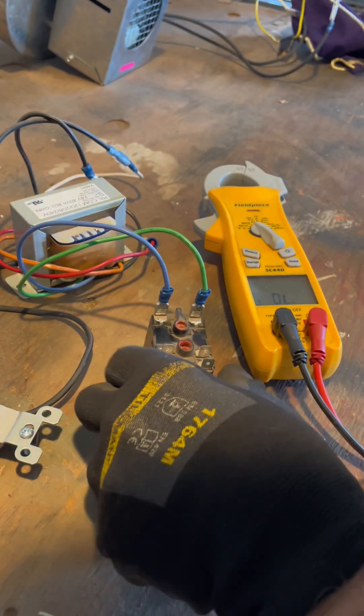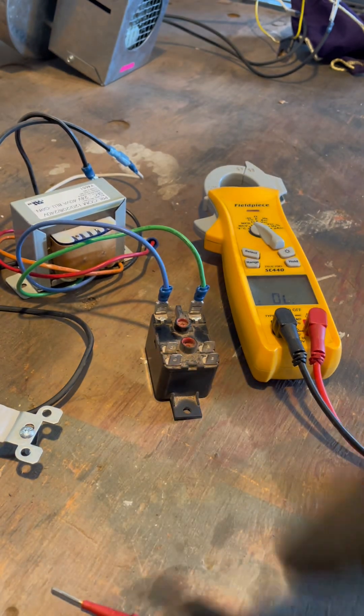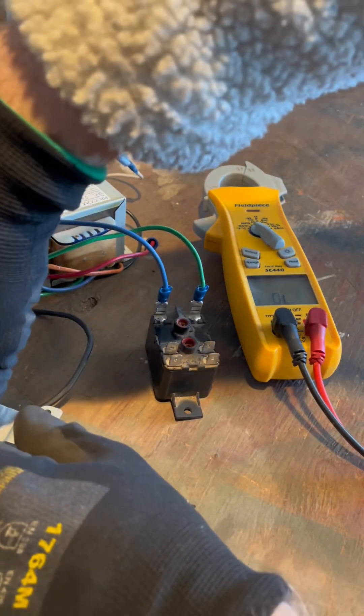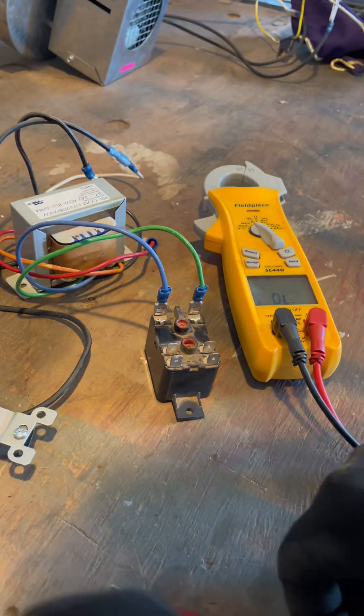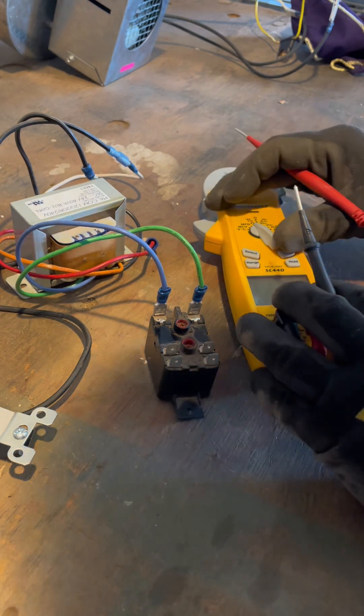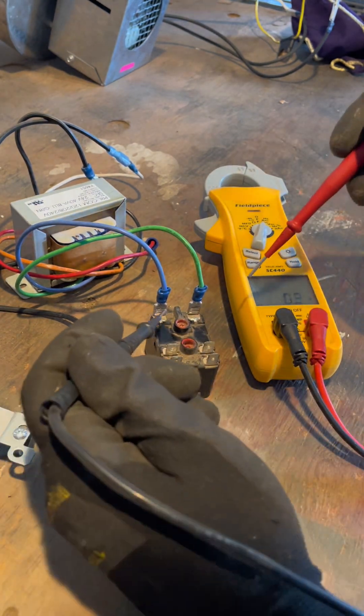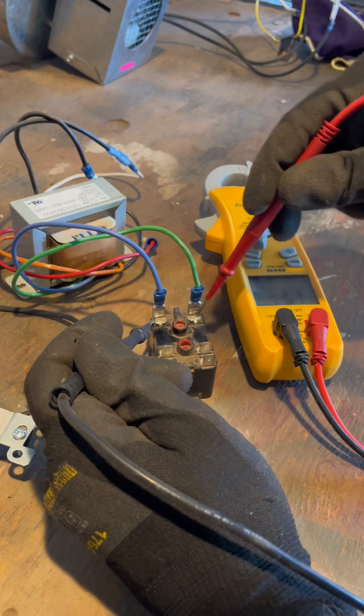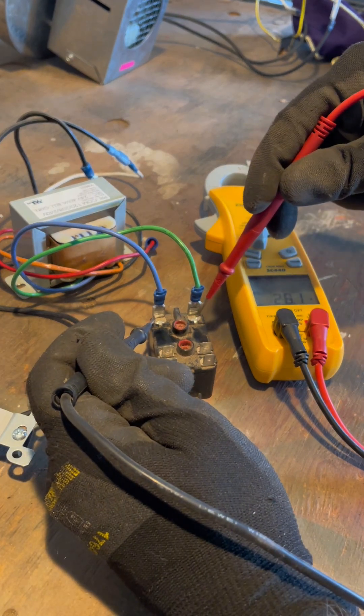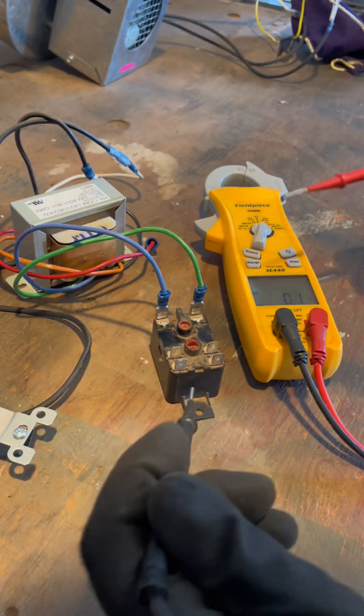So when voltage is applied to the coil, for whatever reason, thermostat calls, I can prove that right here on my meter. I moved over back to volts and I went across and I see 28.1. There's my control voltage present.